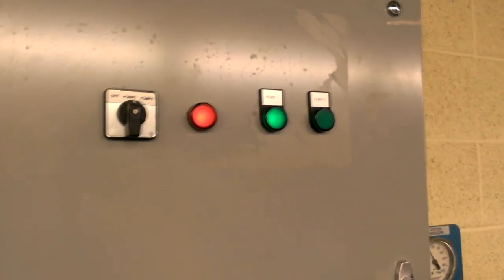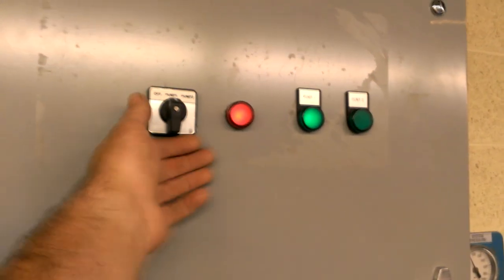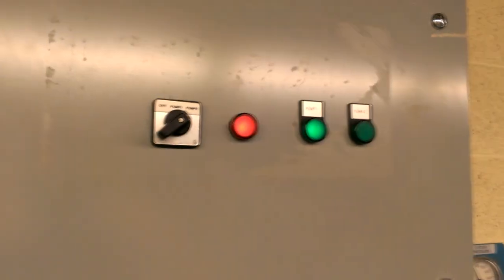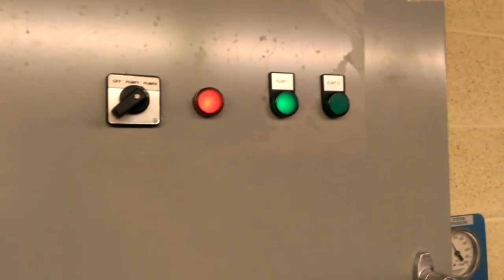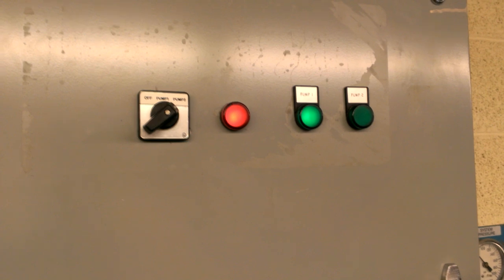Got everything hooked up over here. On the outside, you can just switch it over. The VFD comes to a stop. The delay switches over to the other contactor. Now it's going to start up. There it goes. Now the other pump's running.